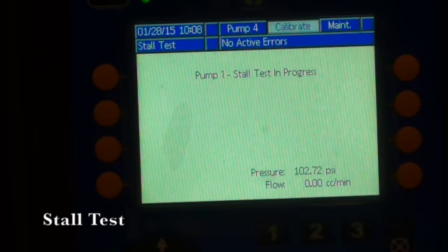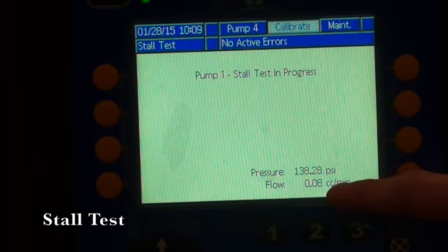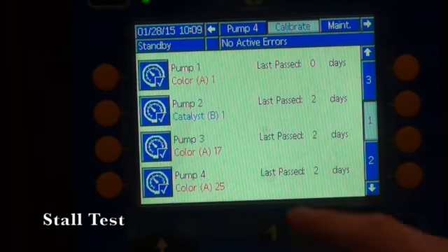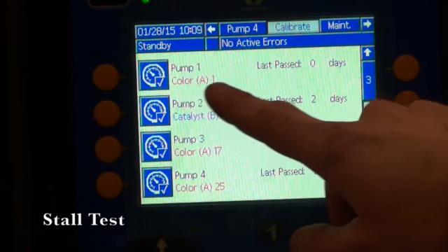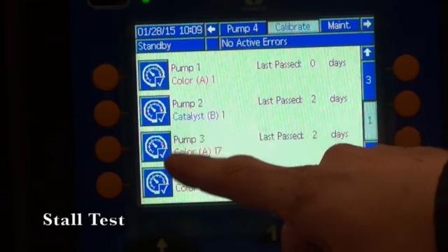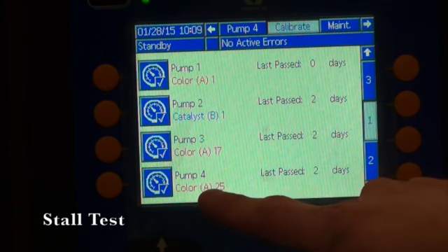That means on the upstroke no fluid is moving, and on the downstroke no fluid is moving. So it holds that for 10 seconds just to make sure everything's fine. And then it will kick back whether it passes or fails. Right now it just switched strokes again, so it's testing this side. With solvent we do have a little bit of flow because it's so light, but there you'll see that pump 1, color 1 passed it. And you can do that individually for each of the pumps.